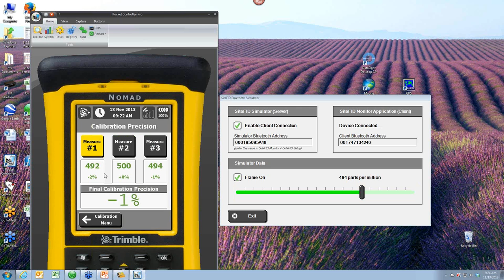So remember, in order to make sure we hit the regulatory requirements, we have to do this 3 times. And again, I'm really whizzing through this. When you're out in the field doing this with your calibration gas, sometimes it can take a little bit longer. And the last thing I'll do is head up towards 500 again real quick here. Make sure that we're where we need to be. And then once we're finished, it will show us that we were plus or minus 5% each of those 3 times. Now remember, if one of these was not within that 5%, you'd have to do it over.